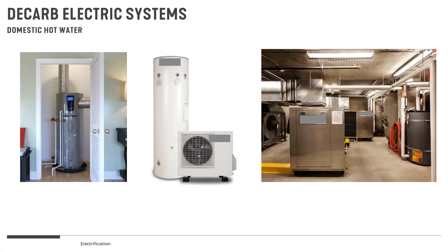One of the really big questions on heat pump water heating is whether you can actually use them in cold climates. There are some heat pumps designed for cold climates—this one in the middle is a CO2 heat pump. CO2 heat pumps actually love being in cold environments. They have what we call a really high lift: they can take very cold air and still extract a lot of heat out of it, making the air really, really cold that leaves. They can work down to about 10 degrees Fahrenheit without losing too much efficiency. After that, they drop off a bit, so you'd need a bigger one. But for most areas in the US, if you're in a cold climate, you'd want to look at a CO2 split heat pump because they're really efficient even in cold weather.